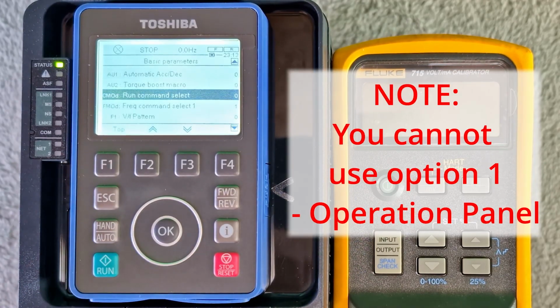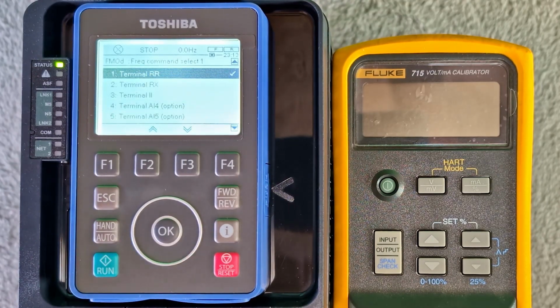Make sure this is set to option 0, Terminal. You cannot use option 1, Operation Panel, for this function. Press OK. Now select Frequency Command, select 1 and press OK. In this example, we will use a 4 to 20 milliamp source, so select option 3, Terminal II, and press OK.